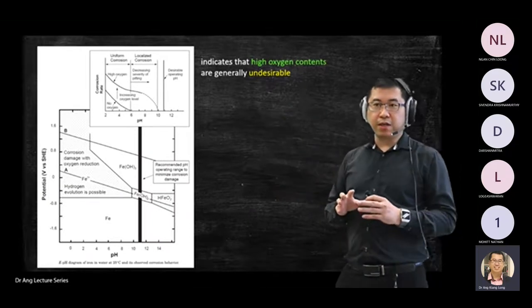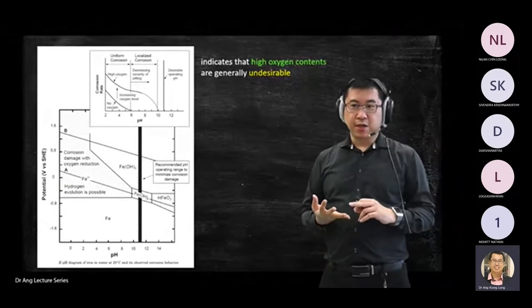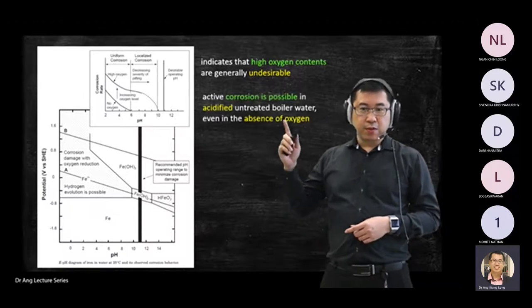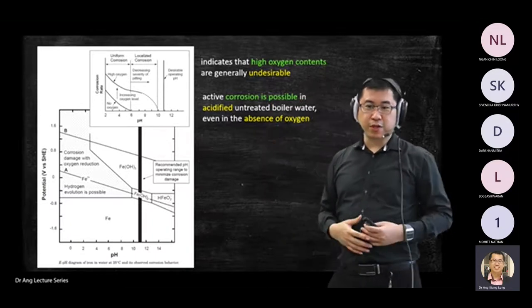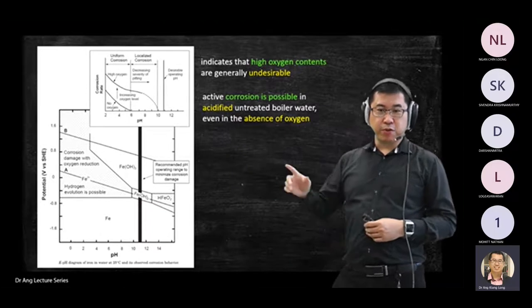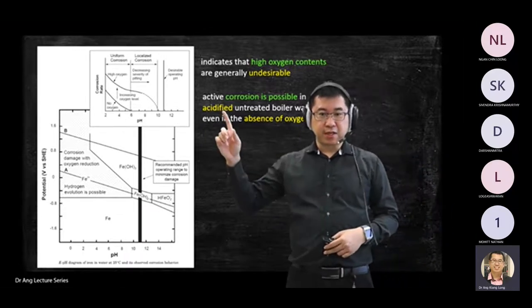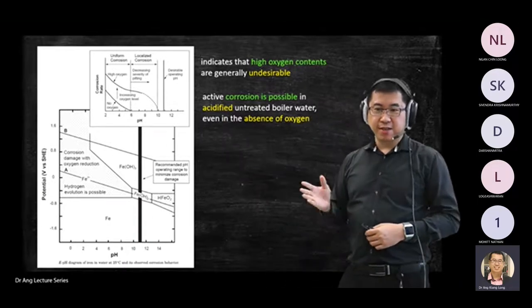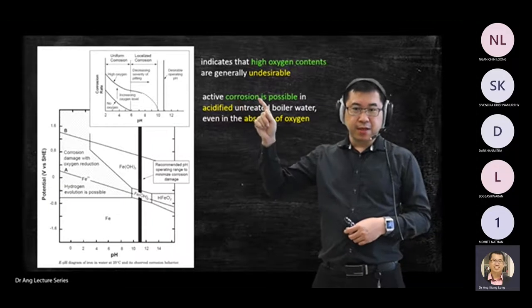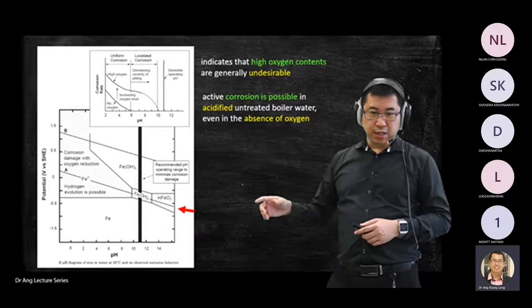For corrosion on metals, we have three factors to carefully control: water, hydrogen, and oxygen. If you supply more oxygen, more corrosion will happen, and more corrosion makes the environment more acidic. If you don't treat the water — just pump in normal water and let corrosion happen — the pH will drop to an acidic level because of the oxygen. And even without oxygen, hydrogen ions will still cause corrosion.